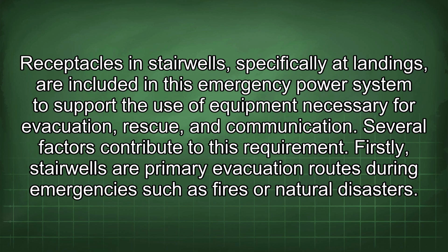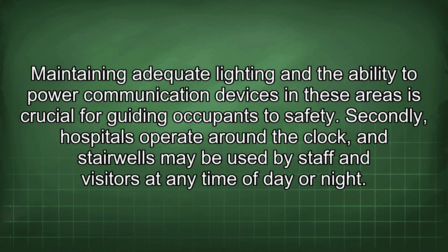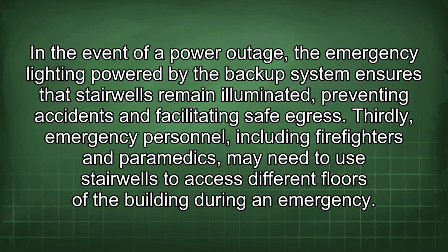Firstly, stairwells are primary evacuation routes during emergencies such as fires or natural disasters. Maintaining adequate lighting and the ability to power communication devices in these areas is crucial for guiding occupants to safety. Secondly, hospitals operate around the clock, and stairwells may be used by staff and visitors at any time of day or night. In the event of a power outage, the emergency lighting powered by the backup system ensures that stairwells remain illuminated, preventing accidents and facilitating safe egress.